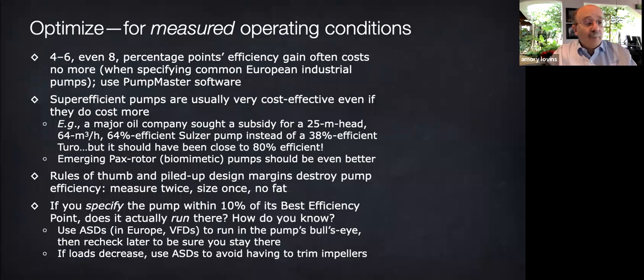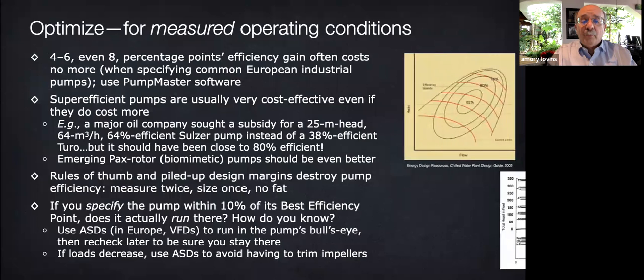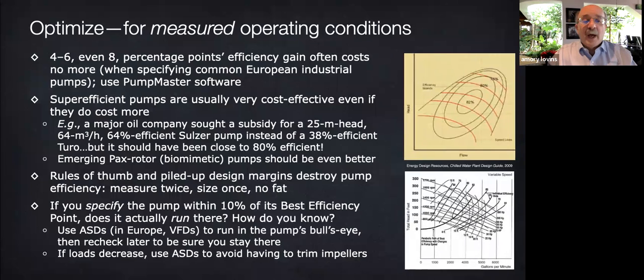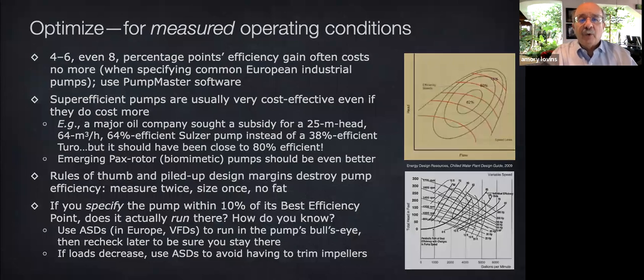Moreover, even a great pump will perform miserably if it is run far from its optimal design point, the so-called bullseye on the efficiency map. So you need to spec it right, adjust its actual operation initially, and then correct it later to seek optimal conditions, maybe as things settle in and wear and some of the variables shift a bit. It's also wise to give yourself more margin by preferring pumps and fans that have a big bullseye, so they're not so sensitive to exactly how well you are matching their optimal conditions.